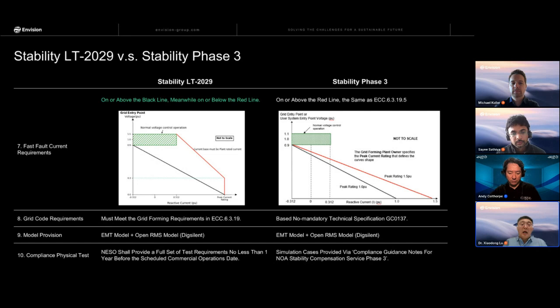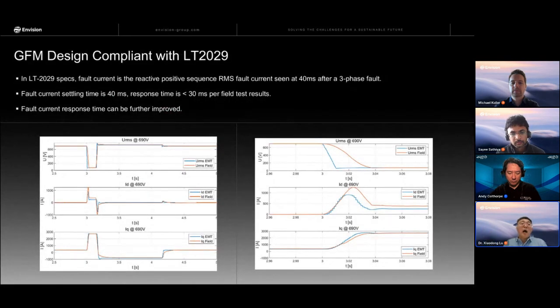As I mentioned just now, after the investigation, we reviewed all our test data on site. Here is one critical part of it, the reactive current injection. Now it's required to be 40 milliseconds after the 3-phase fault. If we look at the figure on the right, the reactive current is on the bottom right. IQ EMT means IQ in simulation, and IQ field means the field test. You can see that after the 3-phase fault occurs at the time of 3 seconds, we have a response time of IQ of less than 30 milliseconds, and the settling time is around 40 milliseconds. So even with our original control design, it meets the requirement very well.